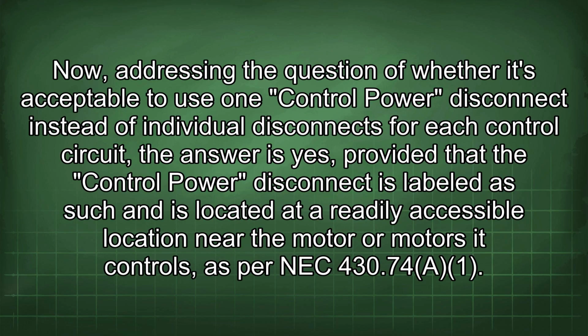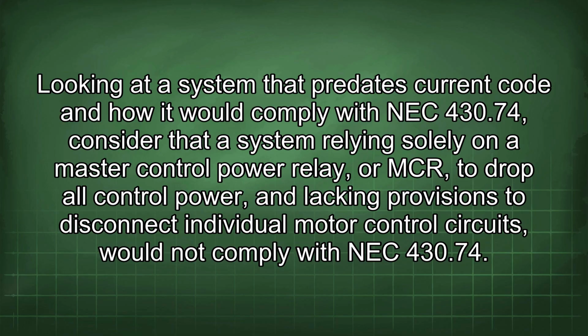Now, addressing the question of whether it's acceptable to use one control power disconnect instead of individual disconnects for each control circuit, the answer is yes, provided that the control power disconnect is labeled as such and is located at a readily accessible location near the motor or motors it controls, as per NEC 430.74 A.